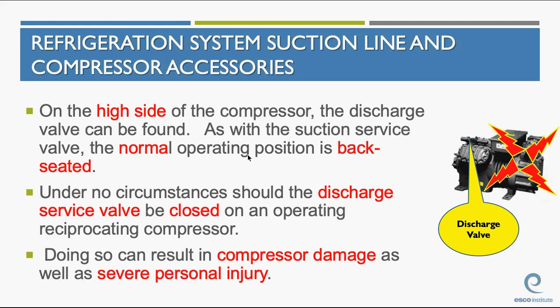On the high side of the compressor, on some compressors, especially semi-hermetic compressors, the discharge valve can be found. As with the suction valve, the normal operating position for the discharge valve is back-seated. Under no circumstances should the discharge valve be closed on an operating compressor. If you close the discharge valve on an operating compressor, in other words, if you front-seat it, the compressor will actually break down inside.